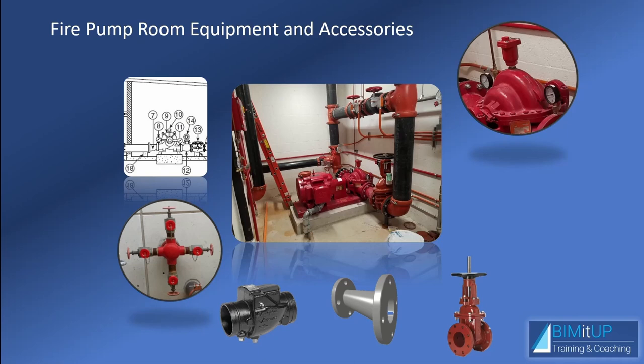Again, for those who just joined, you would have your suction line here. So this is city pressure. Then you have your main isolation valve, which is typically an OS and Y valve. Then an eccentric reducer to prevent air pockets. And then you have your actual pump with a suction and a discharge pressure gauge and an air release.